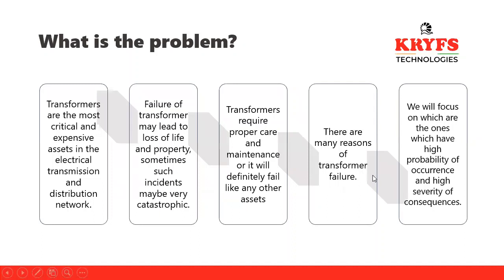What is the problem? Going deeper into what is happening, transformers are the most critical and expensive assets in the electrical transmission and distribution network. Failure of a transformer may lead to loss of life and property, and sometimes such incidents may be very catastrophic. Transformers require proper care and maintenance, or they will definitely fail like any other asset. There are many reasons for transformer failure. We will focus on the ones which have high probability of occurrence and high severity of consequences.